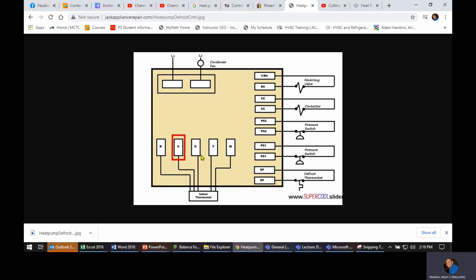So red, common, orange or blue, depending on brand. Most brands use orange to reverse, and that means that it is, I've got to remember how this is. Orange is energized. Let's see. Orange is normally heating, energizes to cooling.